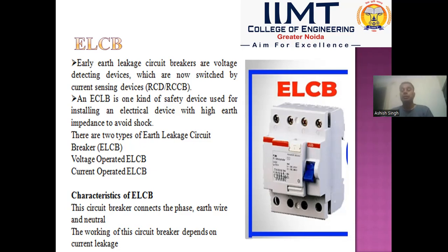In the voltage operated earth leakage circuit breaker, normally the potential difference between the neutral and earth wire is continuously monitored, and if there is a potential difference due to leakage current flowing through the earth wire, ELCB operates. In the current operated earth leakage circuit breaker, a relay is connected between phase wire and neutral wire.